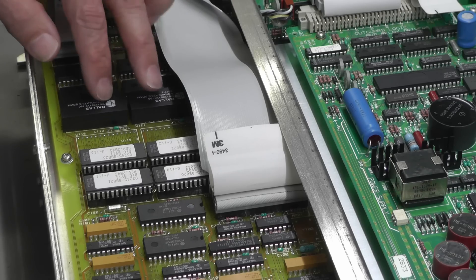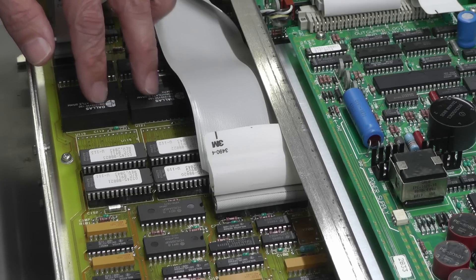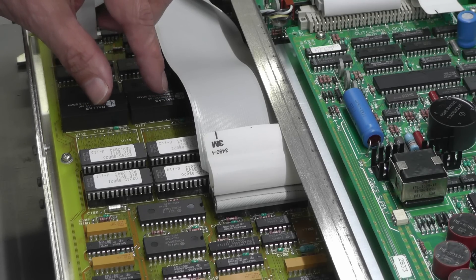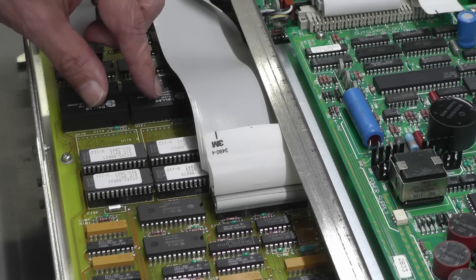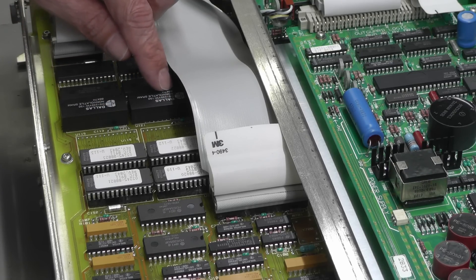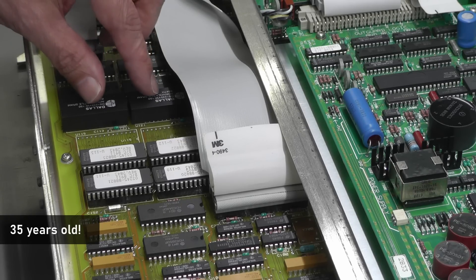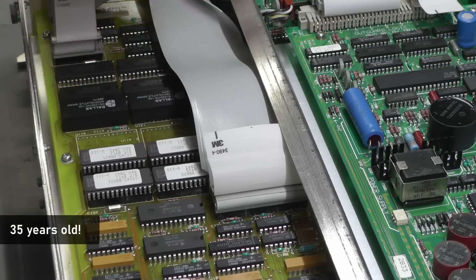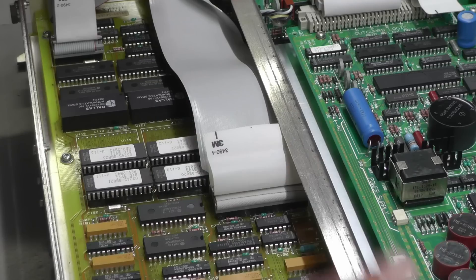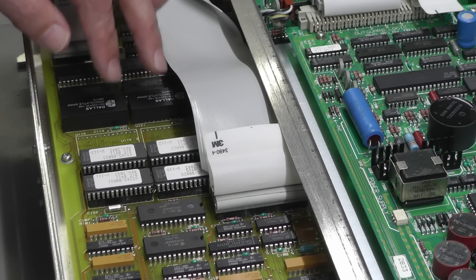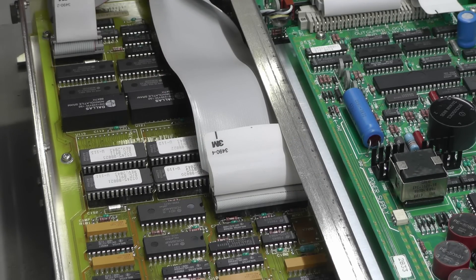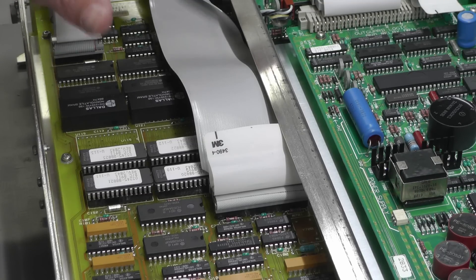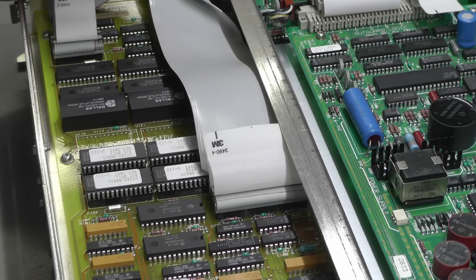Now I'm not going to replace these battery-backed RAMs with the same thing. These have a shelf life anywhere from 5 years to 20 years—it really does vary. And these ones are date stamped 1988, so they are pretty old. Chances are they're flat and that's what's lost the settings that are stored in there and perhaps causing those errors on the front panel.